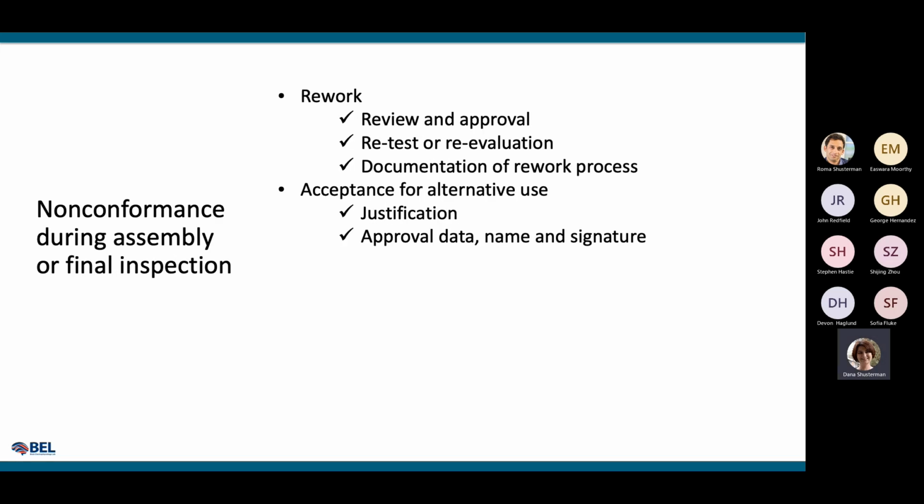If the non-conformance occurred during this step, we will try to evaluate the problem, come up with some solution, and redo the step once again. Alternatively, we might decide that we leave it as it is and use it differently, for example, for marketing purposes. The non-conformance report will include the justification of such decision. Once again, review board should decide the resolution steps.